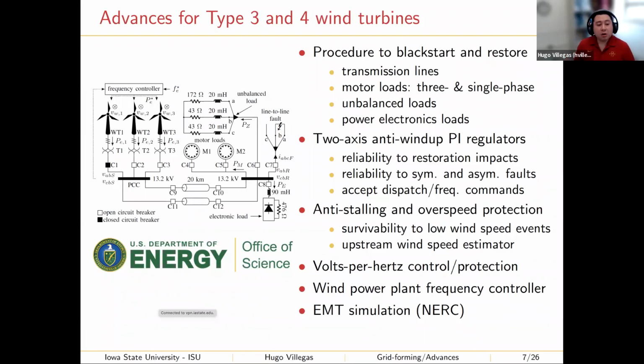But because of that droop, the frequency deviates from rated. So then we need a controller that can steer the frequency of the wind power plant to rated. Of course, we didn't have this problem when we were using, for example, gas turbines. Another challenge is to use electromagnetic transient simulations to reproduce or predict how these processes are going to take place in our future power systems, which was very, very nice.